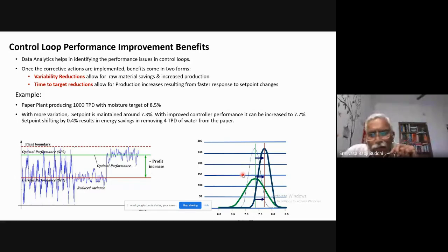I'll be able to reduce the variation by improved performance of the PID controllers. Once I have improved performance, I'll have less variation. So this blue color is basically the histogram coming from the improved performance. Since it has less variation, I'll be able to shift the set point closer to the target. Initially they are operating at about 7.3%. Now, because of improved controller performance, I'll be able to shift it to 7.7%. So I'm able to change the set point by about 0.5%, which results in energy savings.